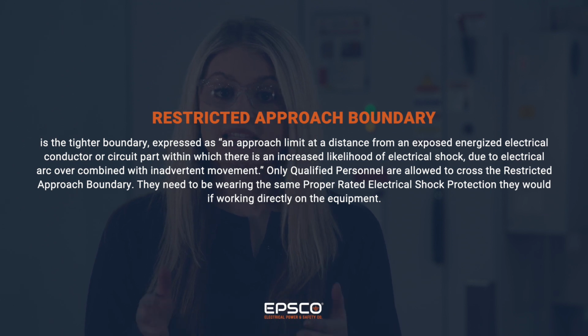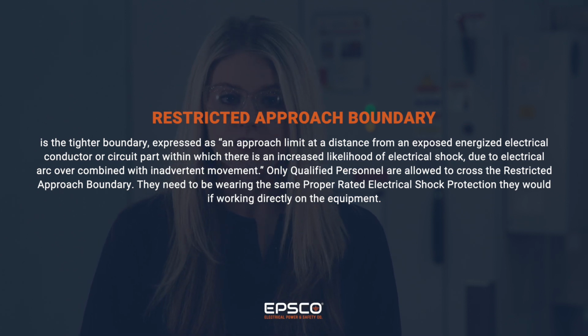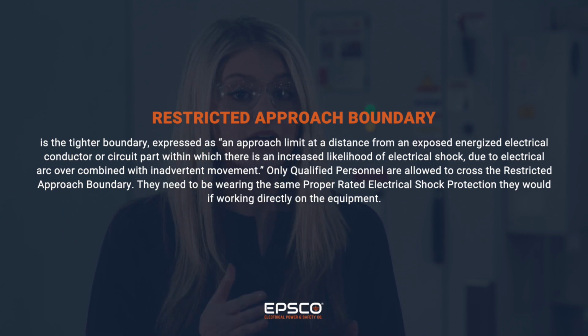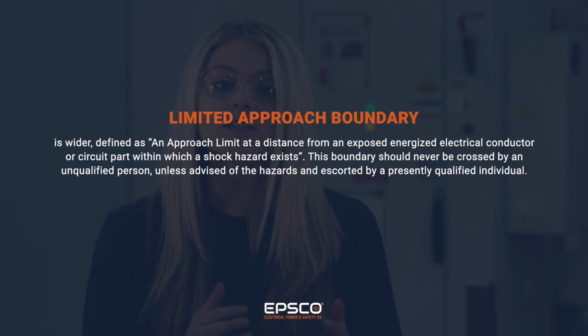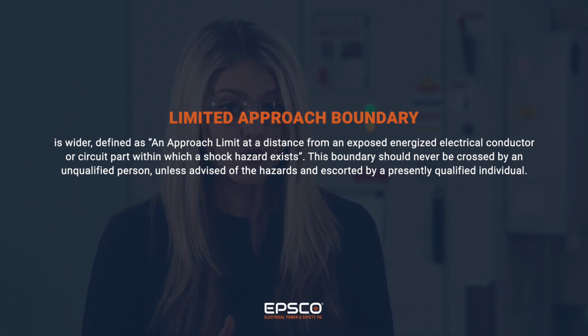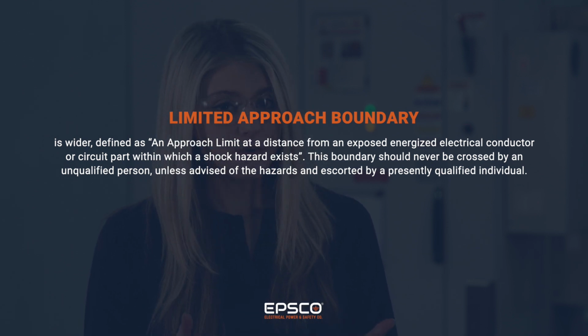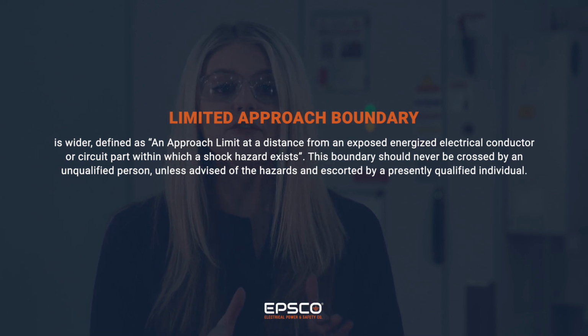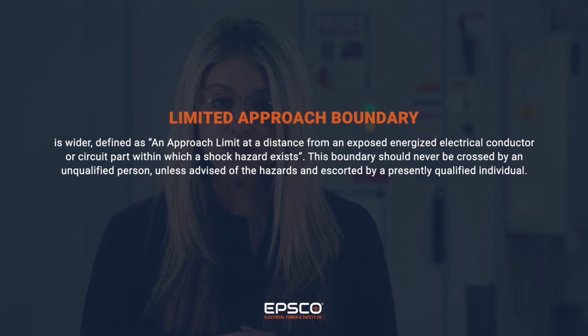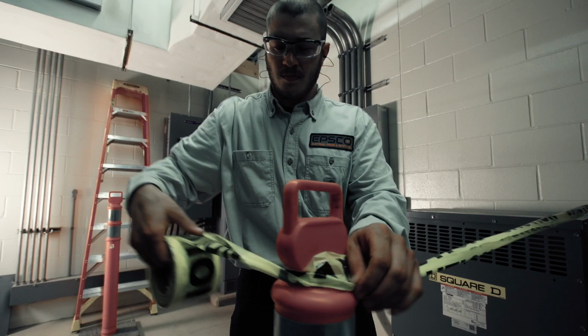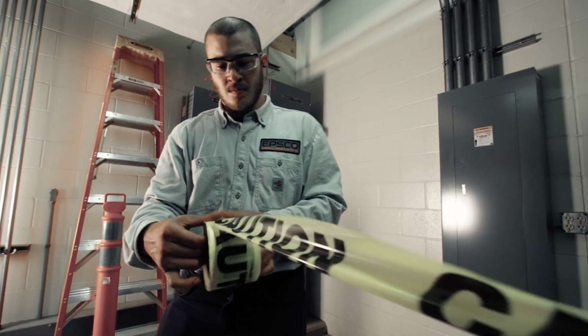The restricted approach boundary is the tighter boundary, expressed as an approach limit at a distance from an exposed energized electrical conductor or circuit part within which there is an increased likelihood of electrical shock due to electrical arc-over combined with inadvertent movement. Only qualified personnel are allowed to cross the restricted approach boundary. They need to be wearing the same properly rated electrical shock protection they would be if working directly on the equipment. The limited approach boundary is the wider, defined as an approach limit at a distance from an exposed, energized electrical conductor or circuit part within which a shock hazard exists. This boundary should never be crossed by an unqualified person unless advised of the hazards and escorted by a presently qualified individual.